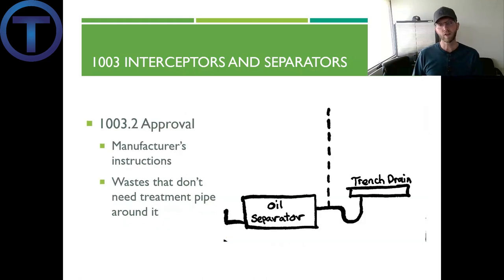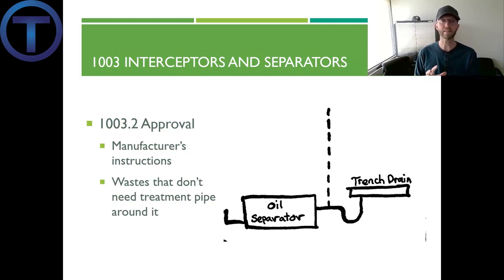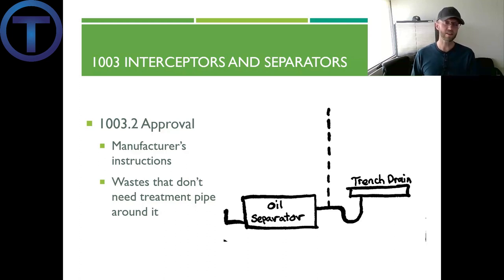Section 1003.2 talks about approvals. Anything we install with the intention of removing things has to meet some standards, and the code requires that we install these according to the manufacturer's installation instructions. Another provision is that wastes that do not need to be treated should not be piped through the separator — they should go around it.